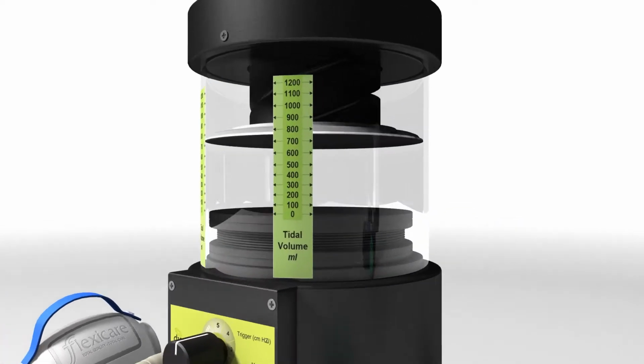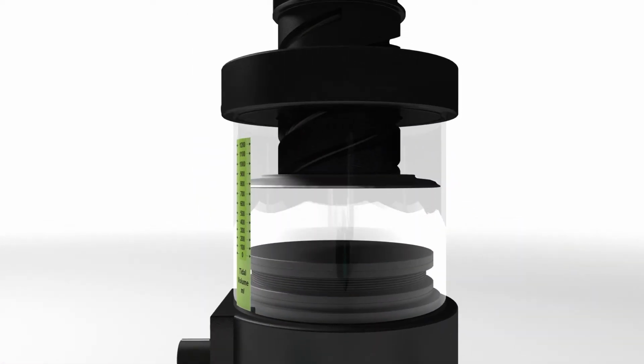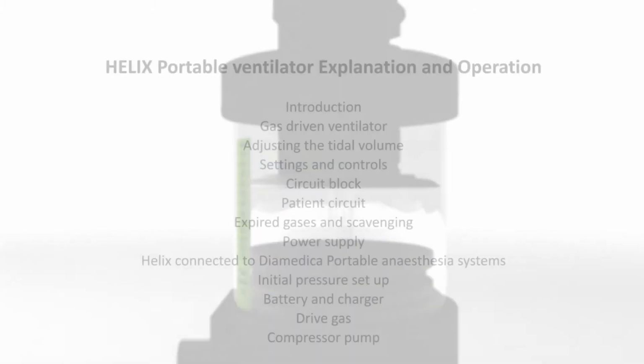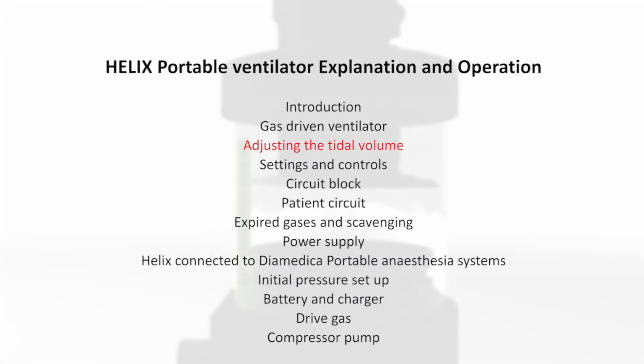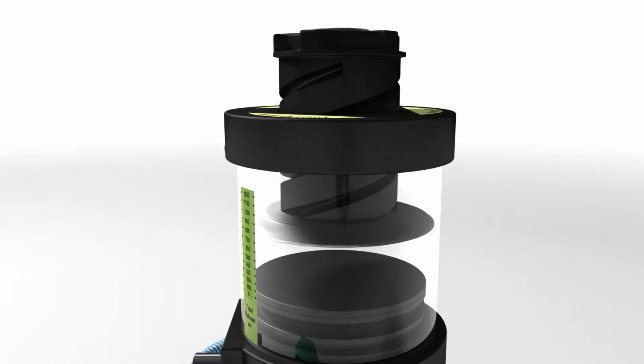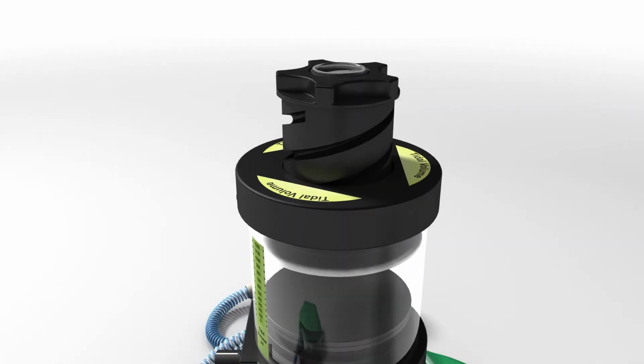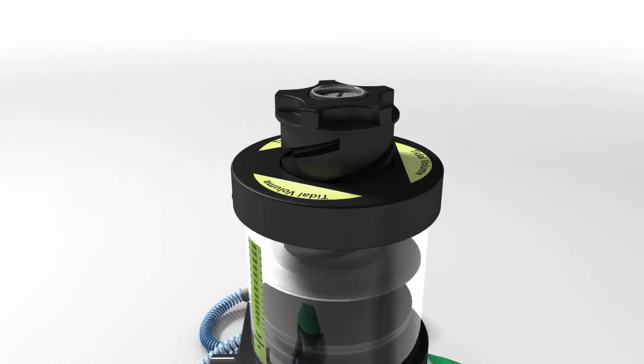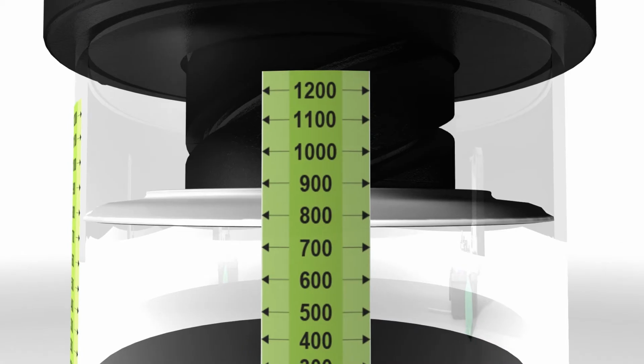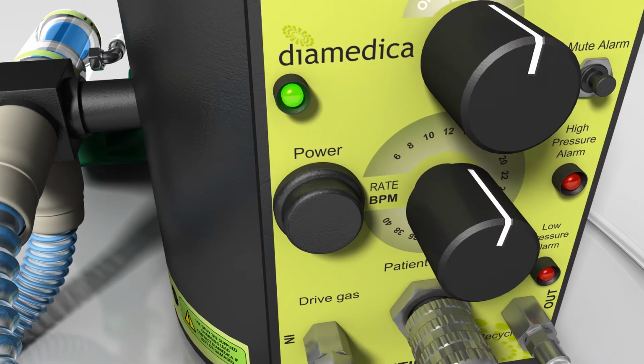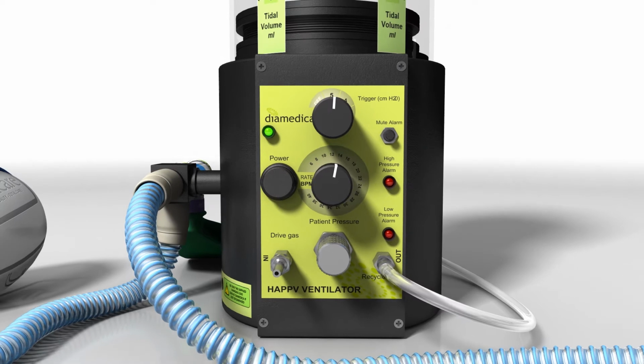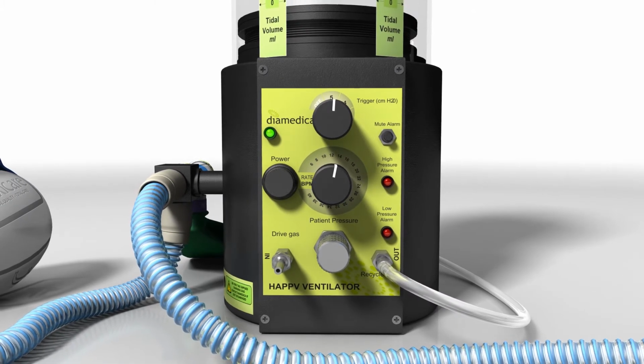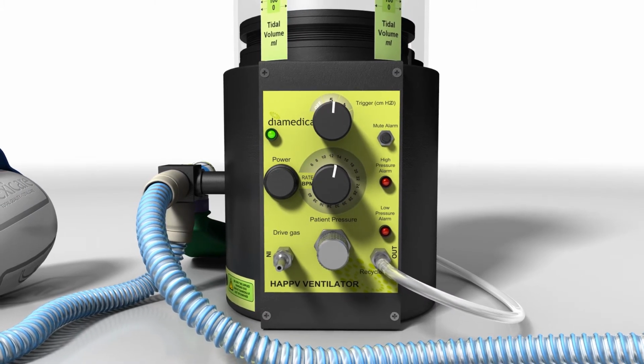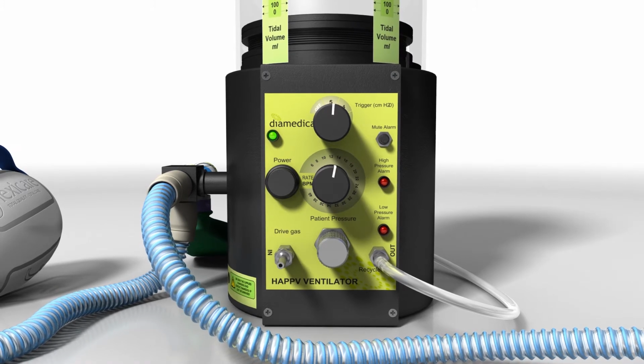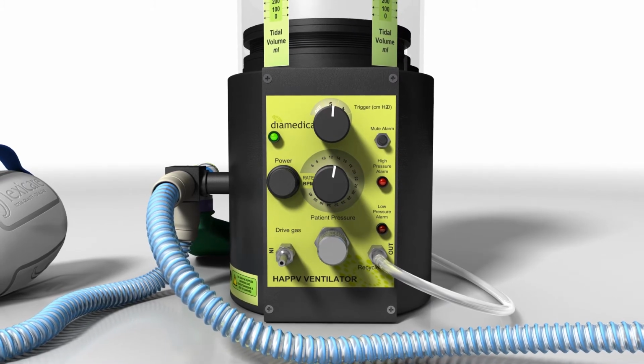The bellows are mounted vertically and driven by a pneumatic piston. The tidal volume is controlled by turning the Helix screw on the top of the bellows and reading the setting here. There is an on-off control with a power-on light. When the ventilator is switched on, initially all three lights show. The power light remains on continuously and a low pressure alarm remains on until there is pressure in the circuit.